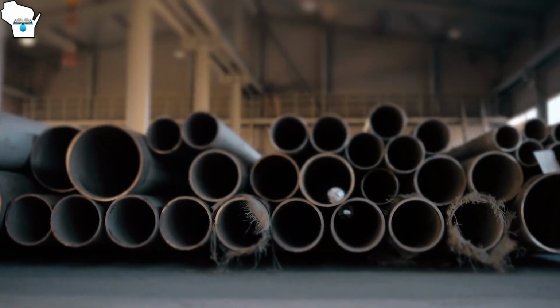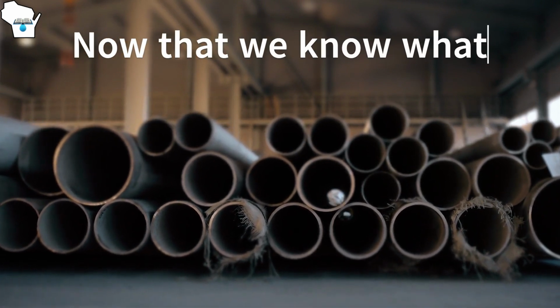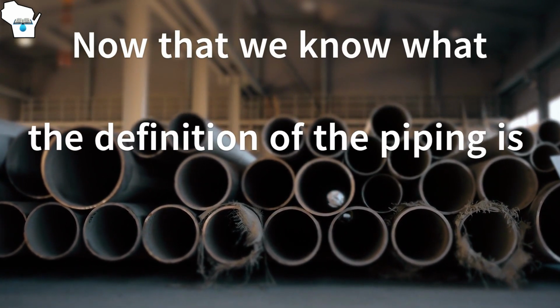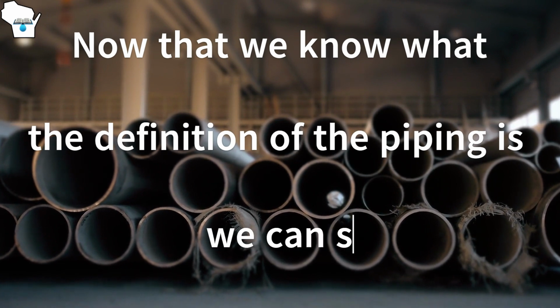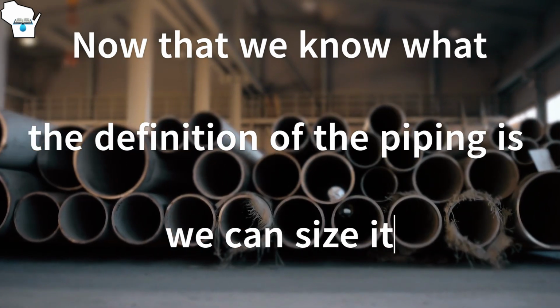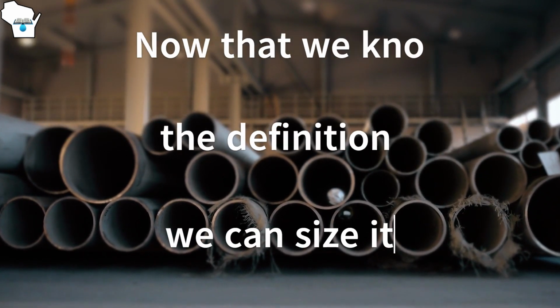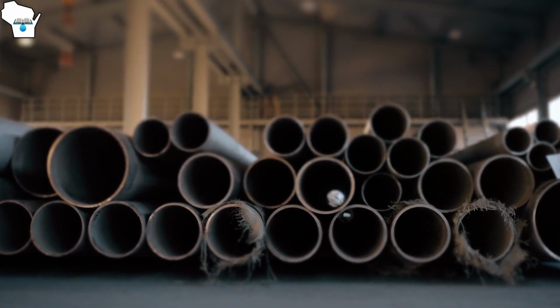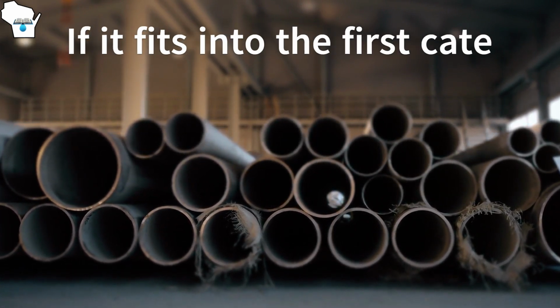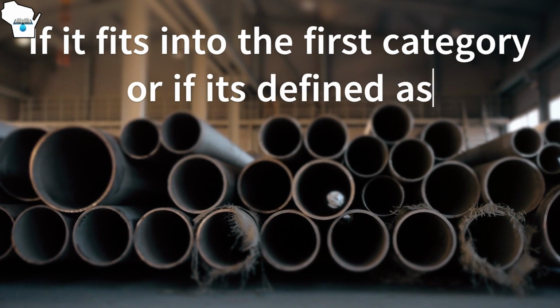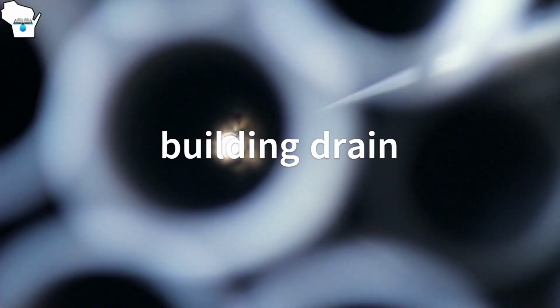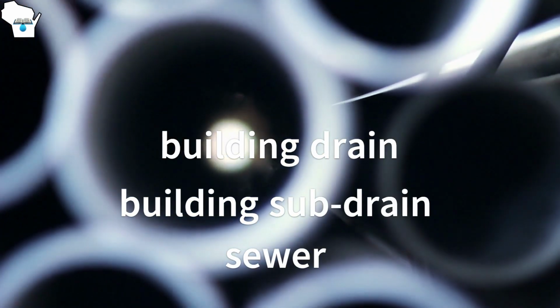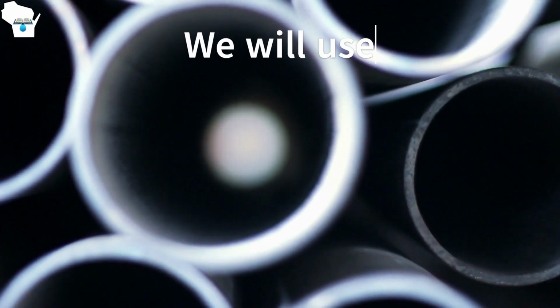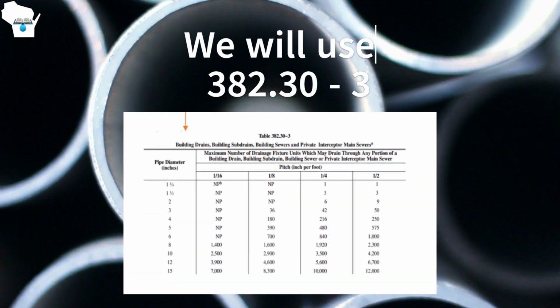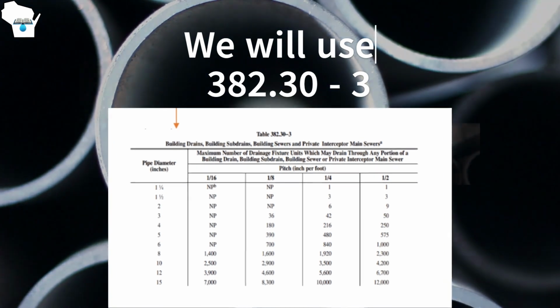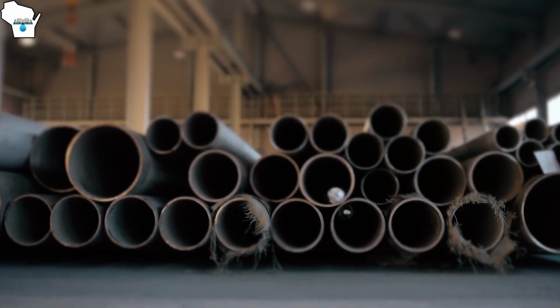Now that we know the amount of DFUs on each pipe and the definition of each of those pipes, we can size it accordingly. If the piece of pipe we are sizing defines as building drain, building subdrain, or building sewer, we will take the DFU load and assign the size based on Table 3 of 382.30 in our Wisconsin Plumbing Code. Keep in mind that the greater pitch allows for a greater amount of DFU on that size of piping.